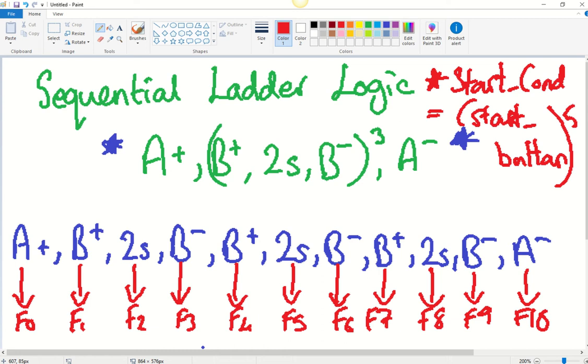There's no stop button mentioned so we won't include that just yet. The sequence will complete and then go back to rest. Also to mention: we're using A and B as double-acting cylinders, but A is driven by a solenoid-activated spring return valve, while B uses a double solenoid valve. So we only have three outputs total — one output for A, and B plus and B minus for the double solenoid.